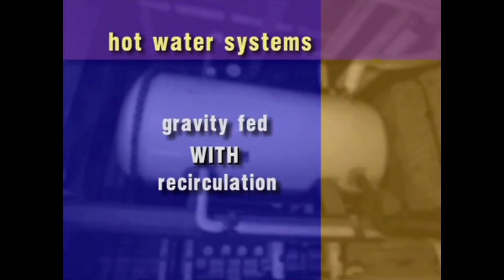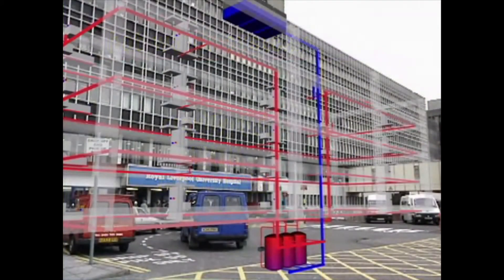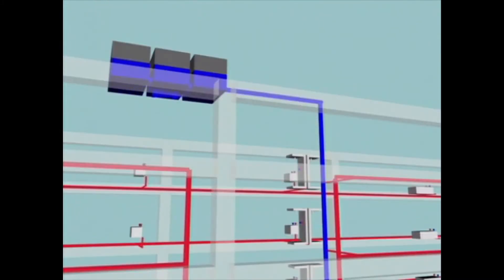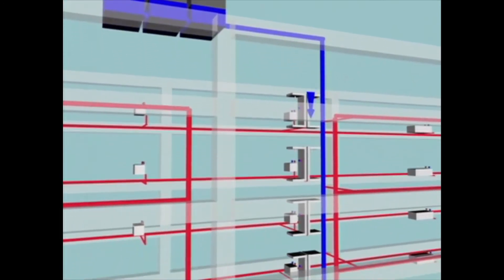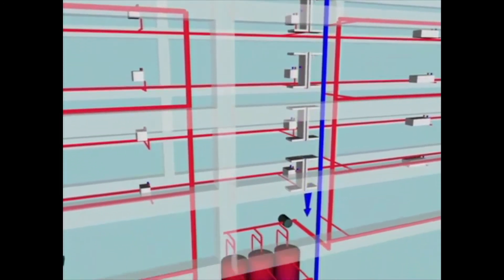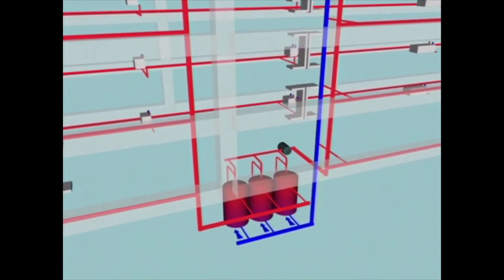A gravity system with recirculation is operated by hospitals, hotels and most commercial buildings. Cold water is stored at a high point within the building or on the roof. There are often multiple cold water tanks feeding into multiple calorifiers which are usually sited in the basement.